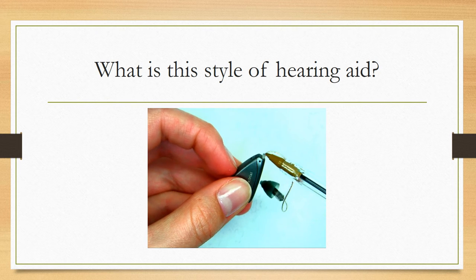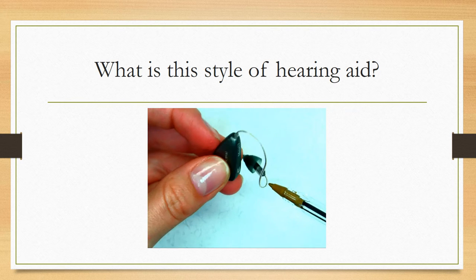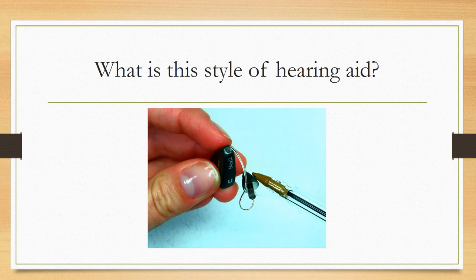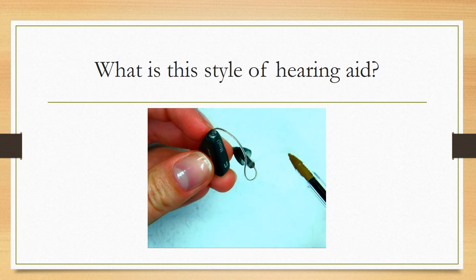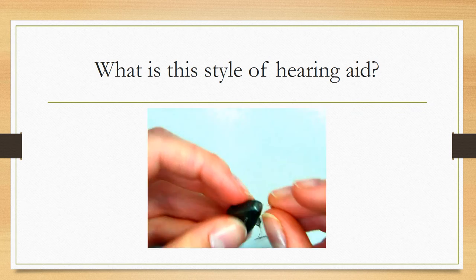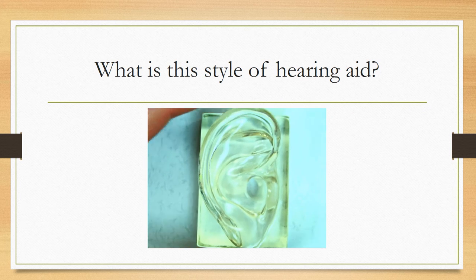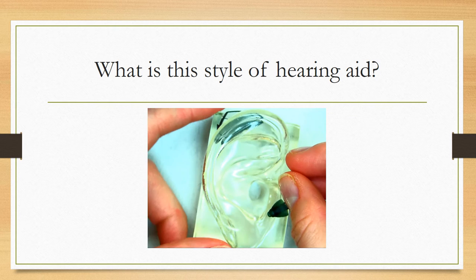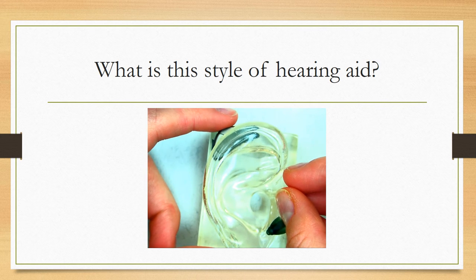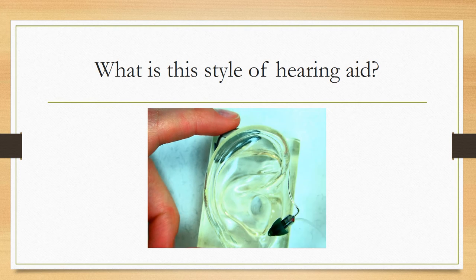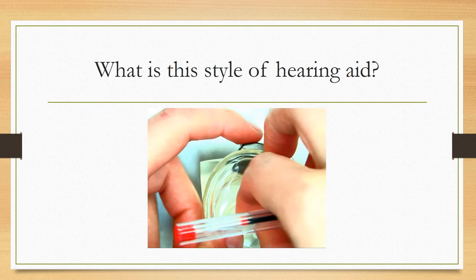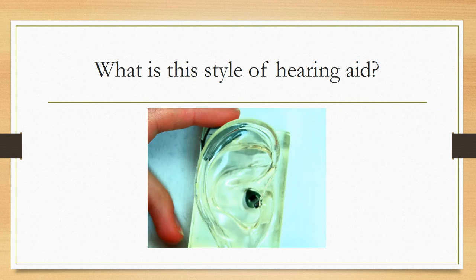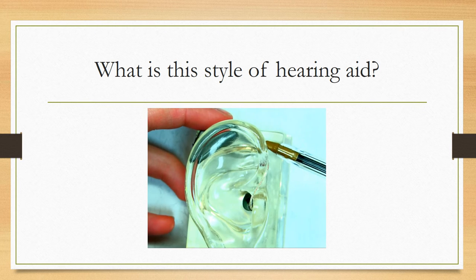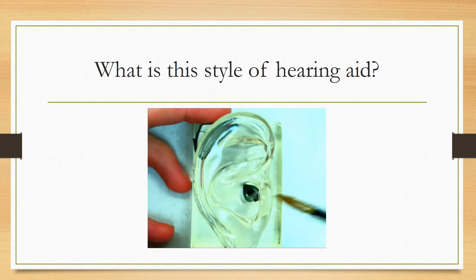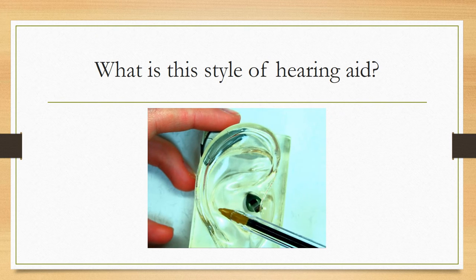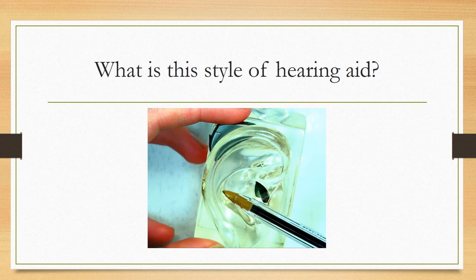And the speaker plugs into the body of the hearing aid up at the top, and it can be removed with a little pin. Okay, that little plastic part there that I was just pointing to is referred to as a sport lock or a concha lock, and it is just a little piece of plastic that helps hold the hearing aid in the ear. And here you can see that I'm putting the hearing aid on the fake ear. I put the body of the aid on first and then put the dome into the ear, and the concha lock is just sitting there laying right in the concha.